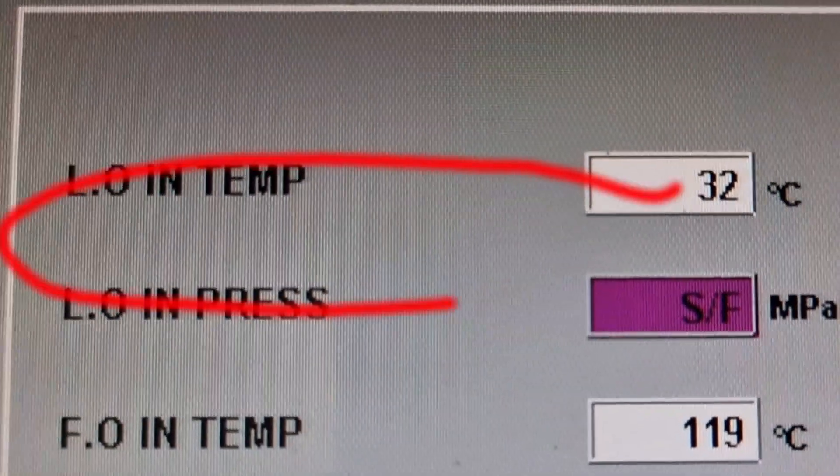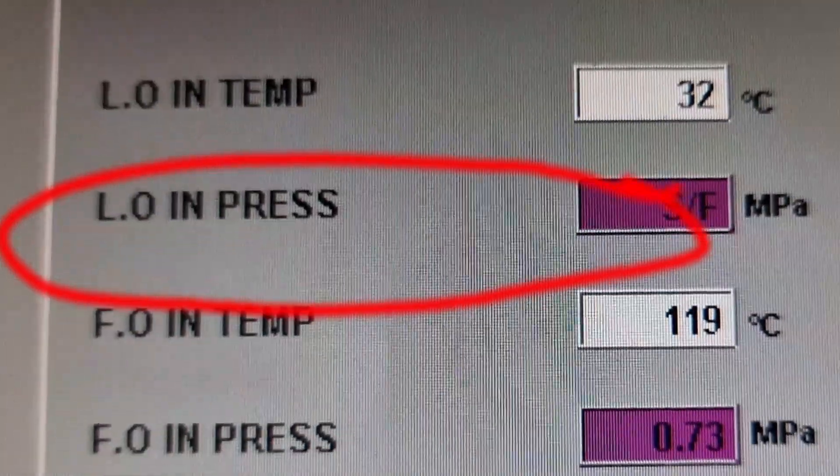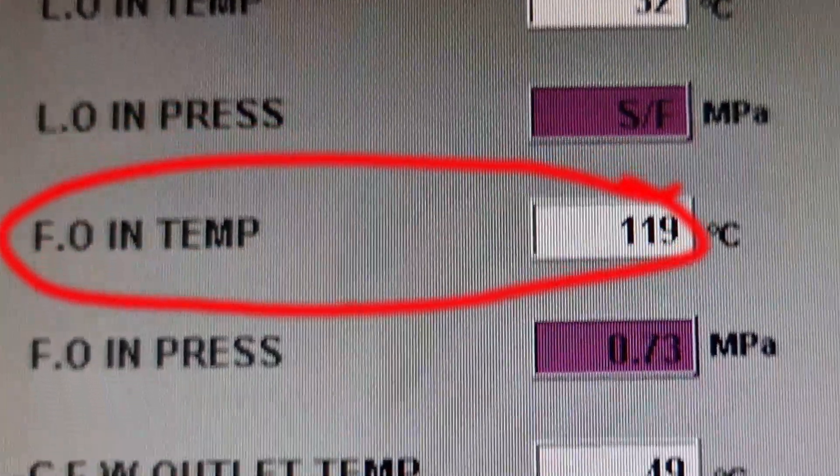So the next wiring will be the lube oil inlet pressure. This is a very important alarm because once the lube oil pressure drops, then the engine will shut. And without this alarm, we cannot just suppress, bypass, inhibit or off-scan the alarm just for the generator to run. Because without this, we don't have shutdown alarm once we have a problem on the lube oil inlet pressure. So we need to find out what is the main cause of this sensor fault, and let's find out.